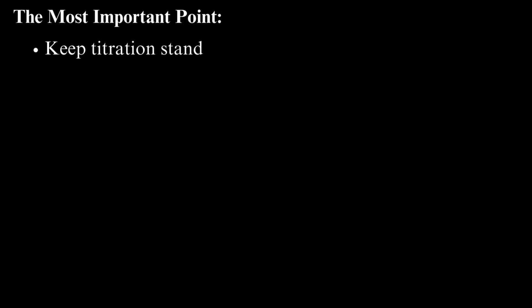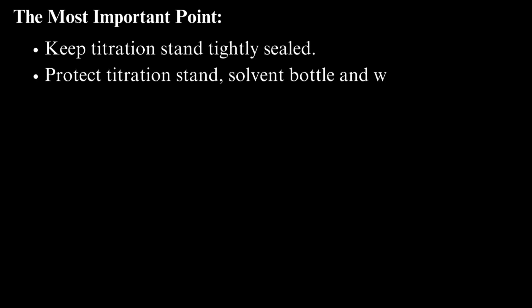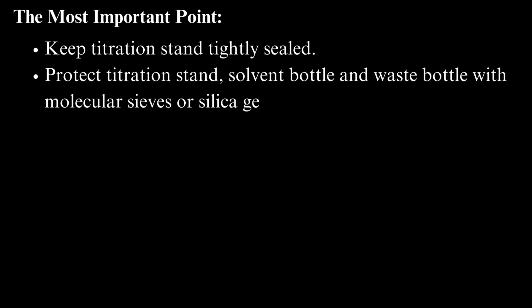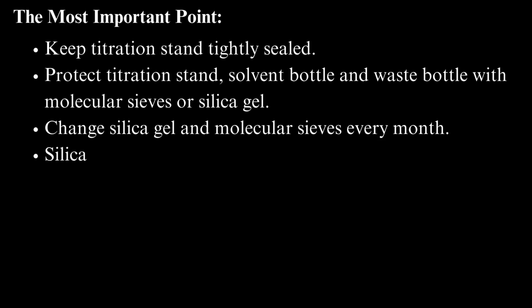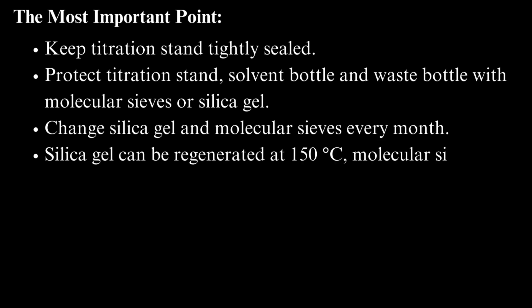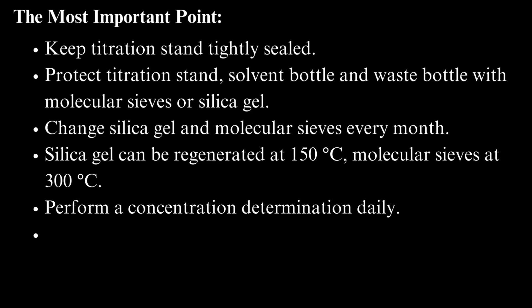The most important point: keep the titration stand tightly sealed. Protect the titration stand, solvent bottle, and waste bottle with molecular sieves or silica gel. Change silica gel and molecular sieves every month. Silica gel can be regenerated at 150°C, molecular sieves at 300°C.